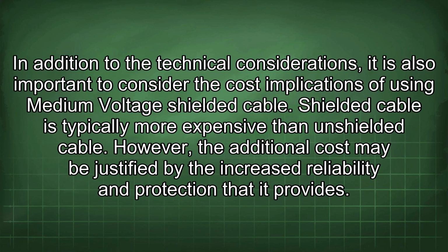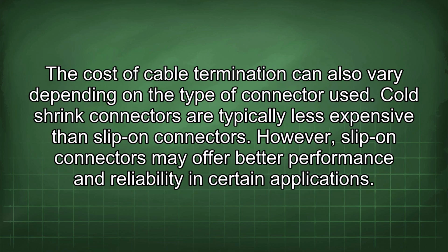In addition to the technical considerations, it is also important to consider the cost implications of using medium-voltage shielded cable. Shielded cable is typically more expensive than unshielded cable. However, the additional cost may be justified by the increased reliability and protection that it provides. The cost of cable termination can also vary depending on the type of connector used. Cold shrink connectors are typically less expensive than slip-on connectors. However, slip-on connectors may offer better performance and reliability in certain applications.